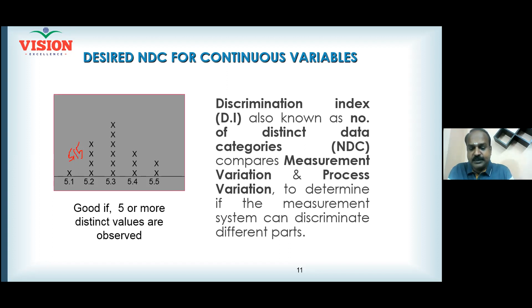Suppose I change the resolution to 0.05. Earlier, what was the resolution? 0.1. And so it has produced an NDC of 5. And now I go for a better resolution, 0.05. Now, between 5.1 and 5.2, one more reading is possible. Can you tell me what is that reading? 5.15. That means within your working range of 5 and 5.5, you will now produce 10 different readings. Am I right? That means what is your NDC now? 10. NDC has become 10, right? So higher NDC is good, and minimum requirement is 5. If 5 also is not happening, any measurement system is considered inadequate. Is that clear?